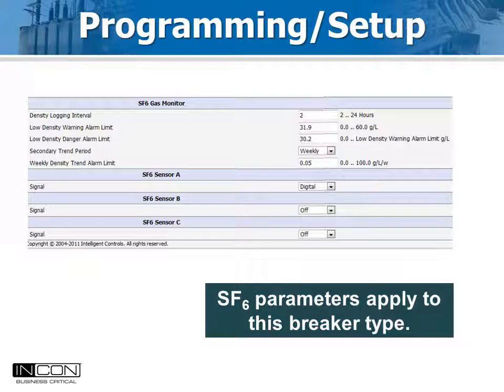This part of the screen sets up the SF6 density parameters. Here, the warning and lockout limits for SF6 gas are entered along with the sensor type. Digital true density sensors are standard with the Optimizer 2, but analog temperature compensated pressure sensors giving a 4 to 20 milliamp signal can also be used.